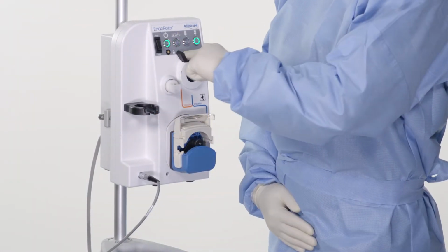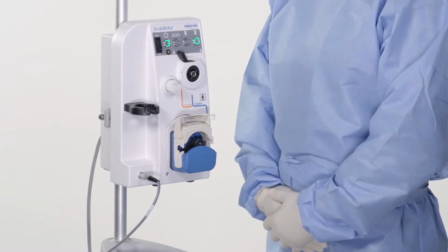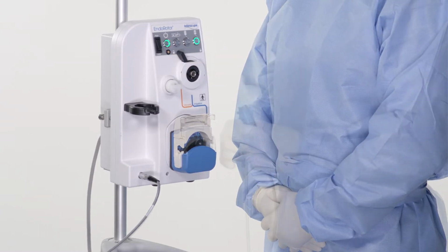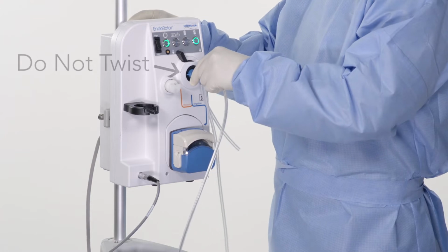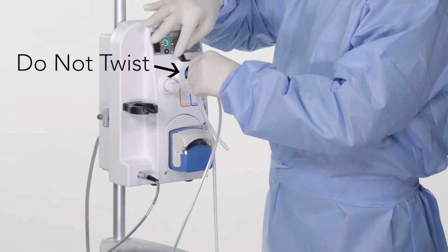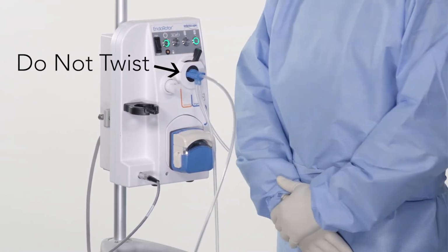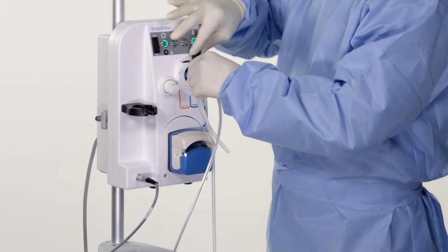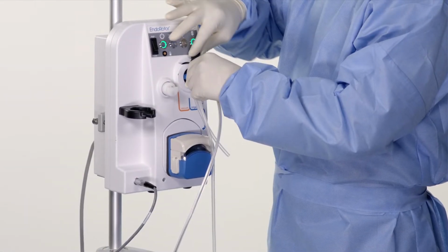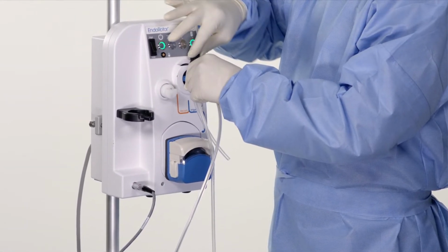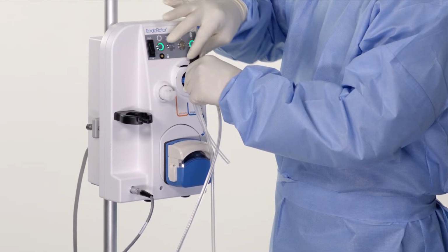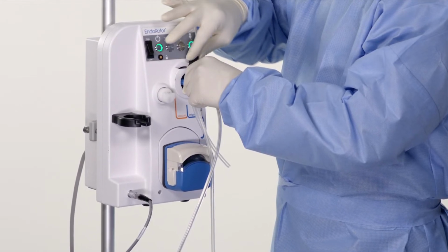Ensure the catheter interface on the console is in the unlocked position. Insert the catheter's proximal housing into connection. Ensure hex connection aligns. Gently push catheter's housing completely inward and rotate locking lever right into locked position. Maintain forward pressure when inserting the catheter.